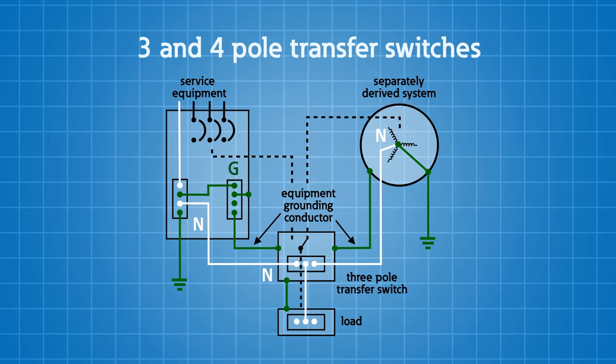So when I have a neutral conductor bonded and grounded in two separately derived systems, remember, I have it grounded and bonded in my service panel. I have it grounded and bonded in my generator. I need to make sure that I only have one place where that occurs. And to get that done, I need to switch the neutral in the transfer switch. So that means I would need to have, say for example, a four-pole transfer switch. If I do that, I put a four-pole transfer switch in, I switch the neutral, everything is fine.